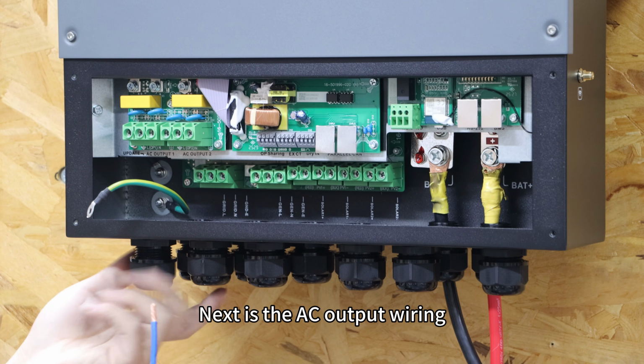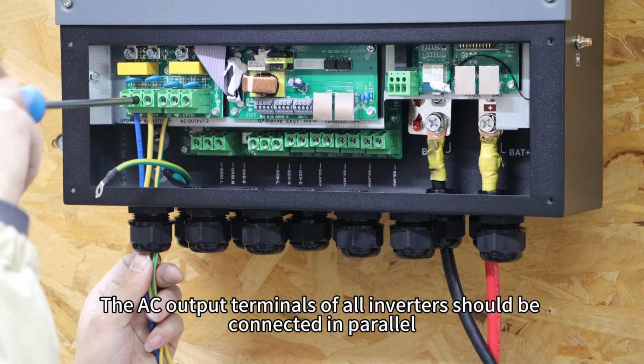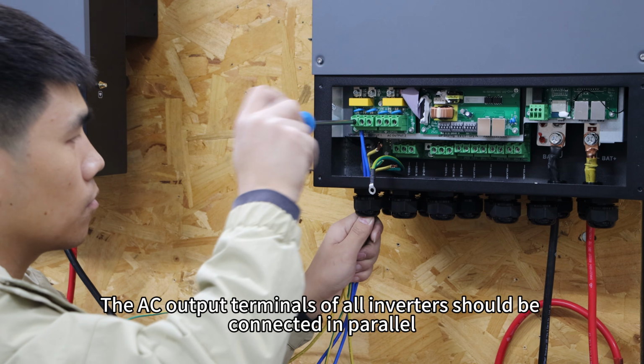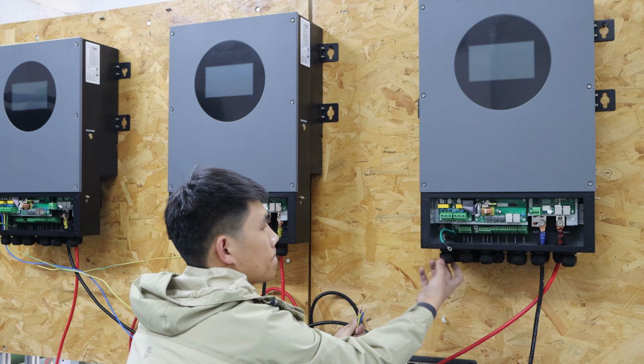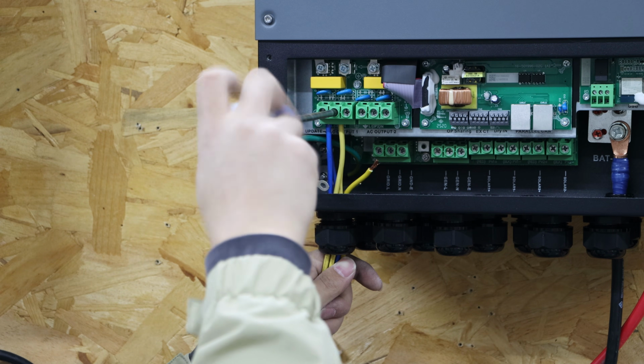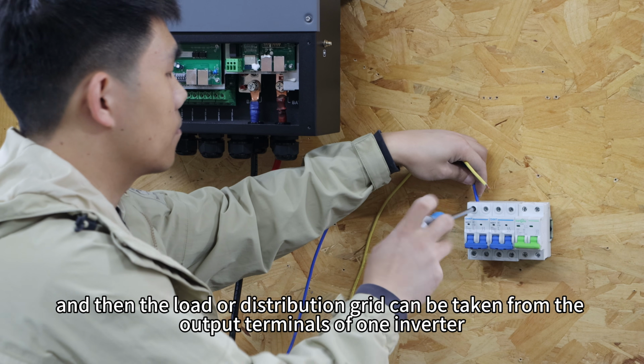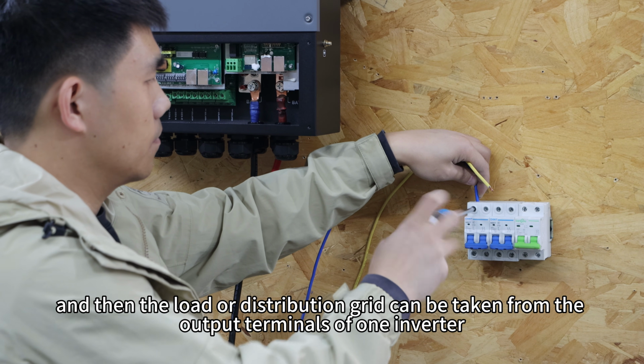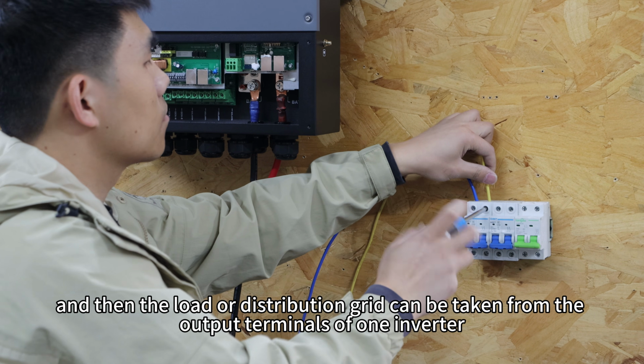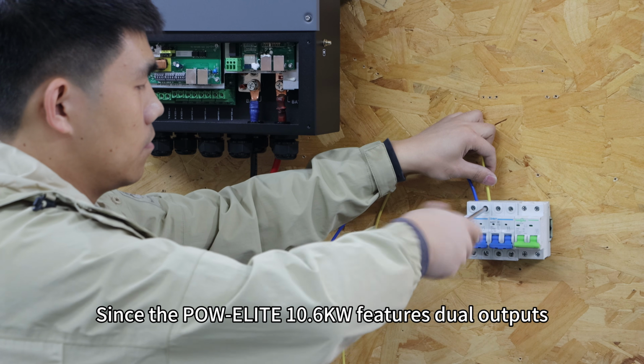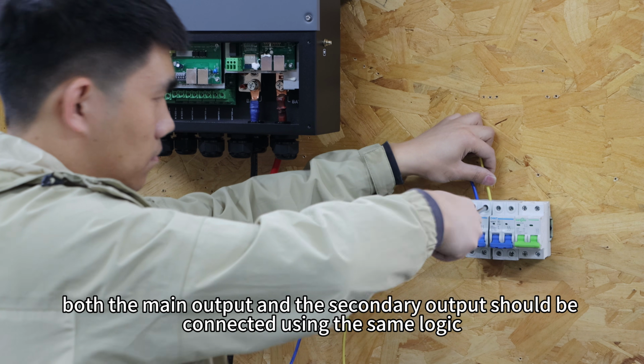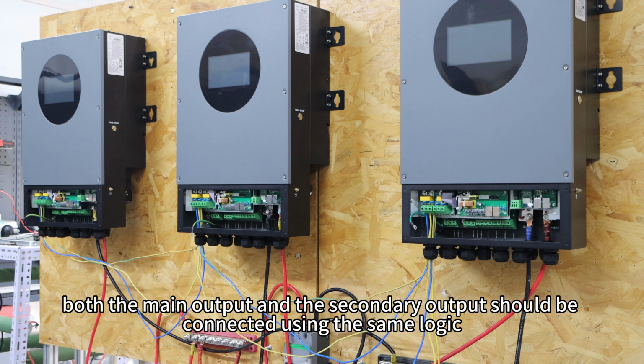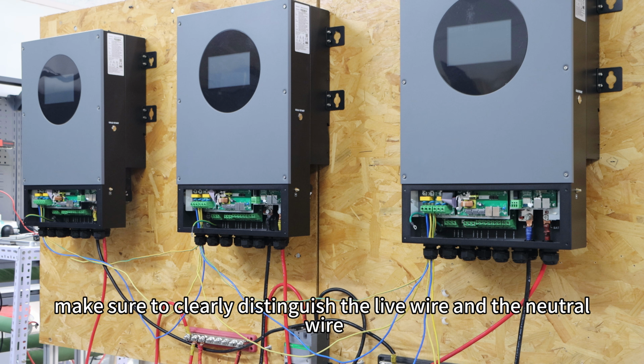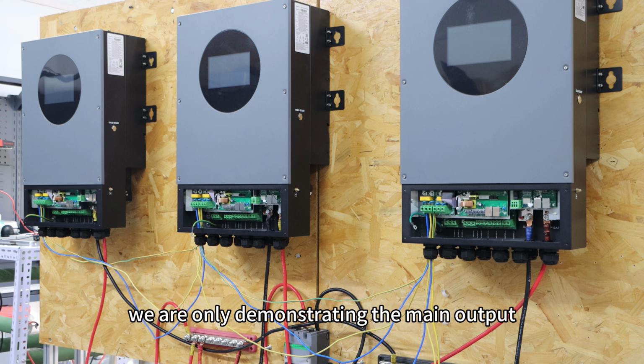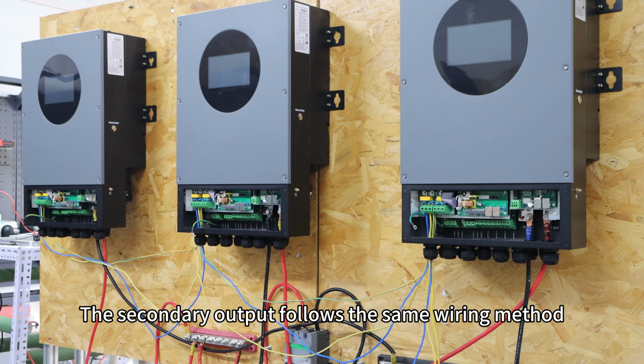Next is the AC output wiring. The AC output terminals of all inverters should be connected in parallel. And then the load or distribution grid can be taken from the output terminals of one inverter. Since the POW-ELITE 10.6KW features dual outputs, both the main output and the secondary output should be connected using the same logic. During wiring, make sure to clearly distinguish the live wire and the neutral wire. Here we are only demonstrating the main output. The secondary output follows the same wiring method.